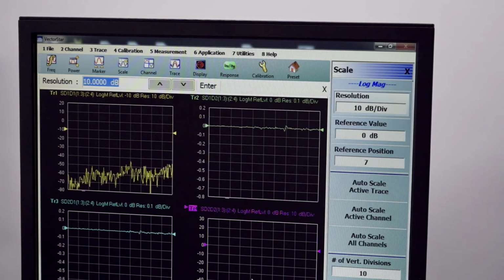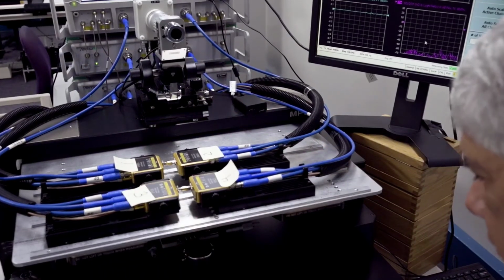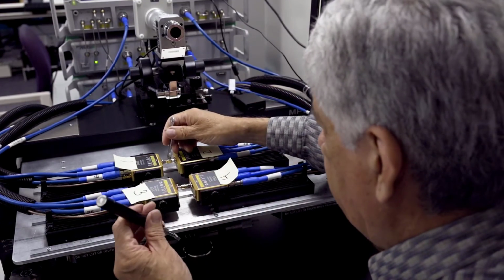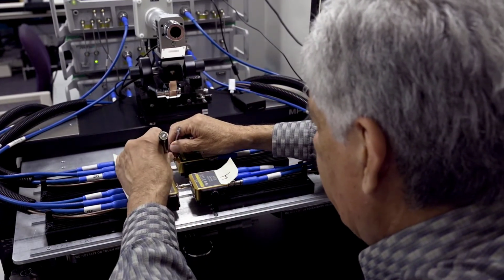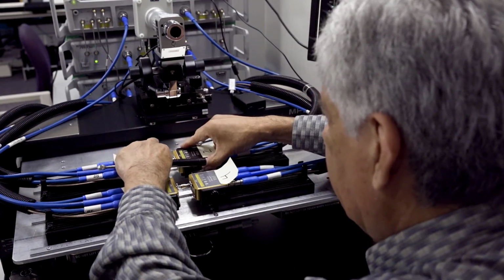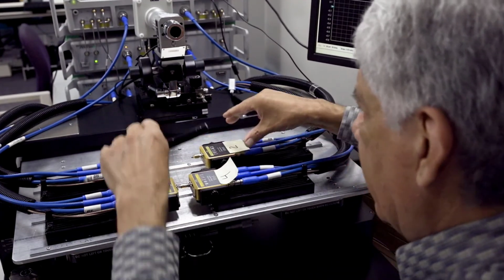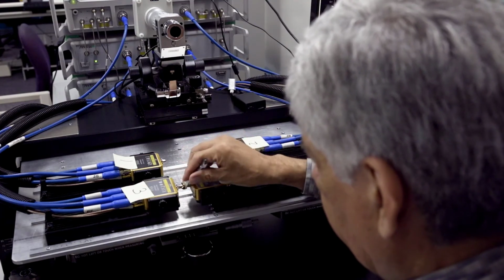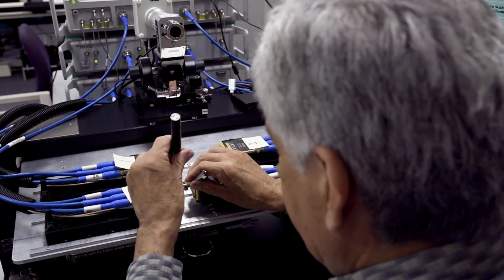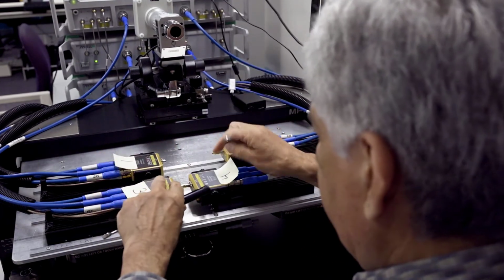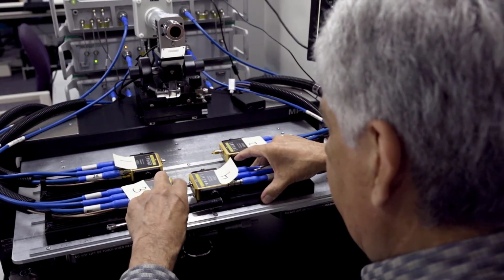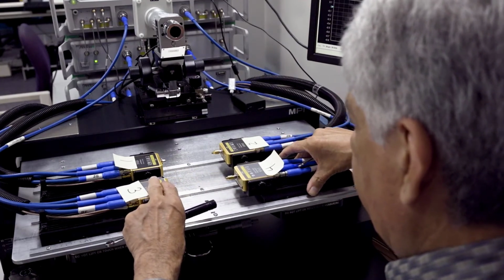Now what I could do is connect a couple of coaxial lines between the ports to see how the calibration looks in terms of a very low loss insertion loss measurement. So I disconnect my test ports, and again you want to be real careful not to break the connection between the adapter and the test ports, because that could certainly induce some connector glitches, or at least some variations due to connector repeatability.